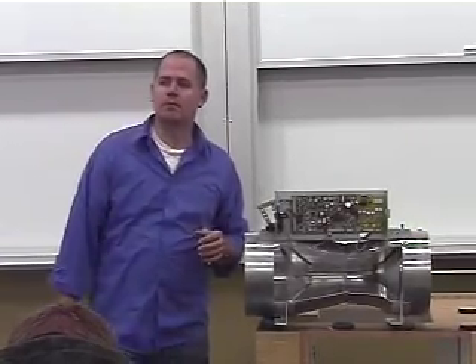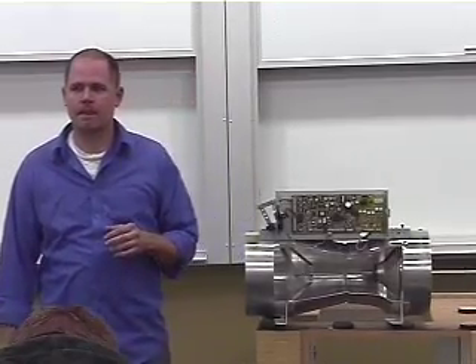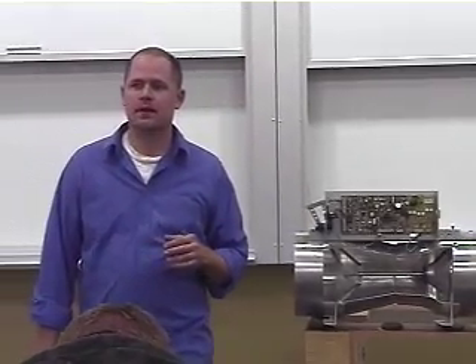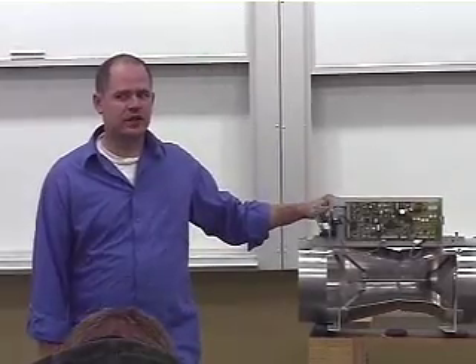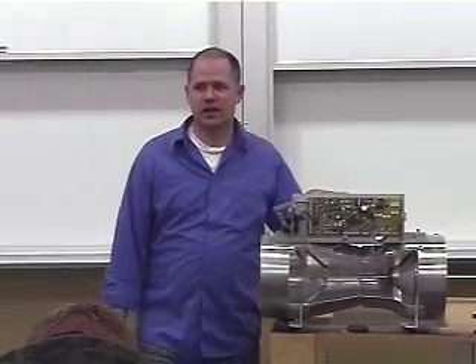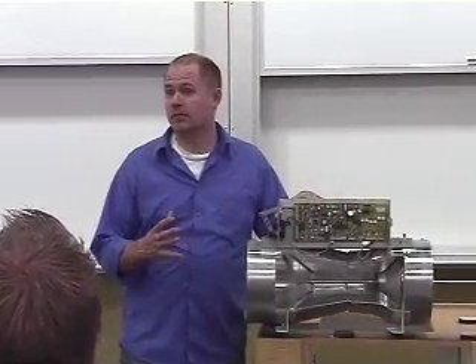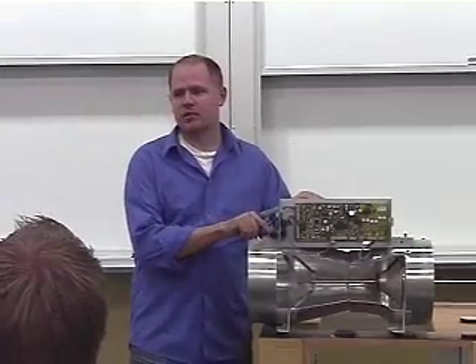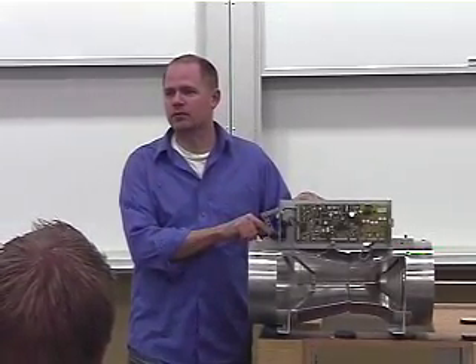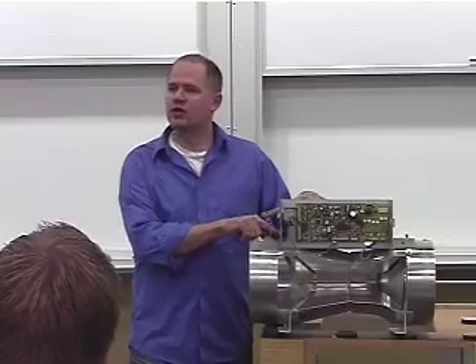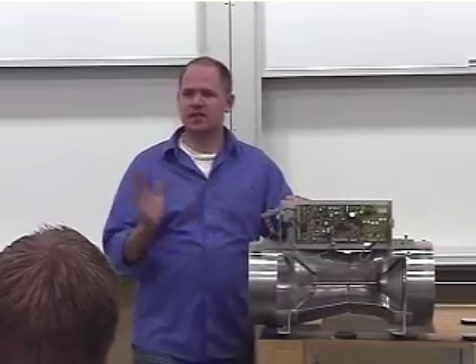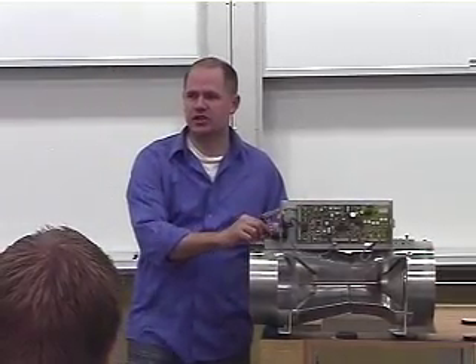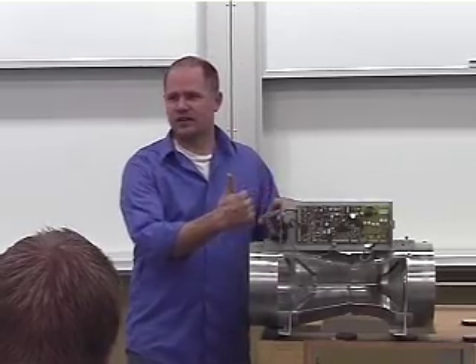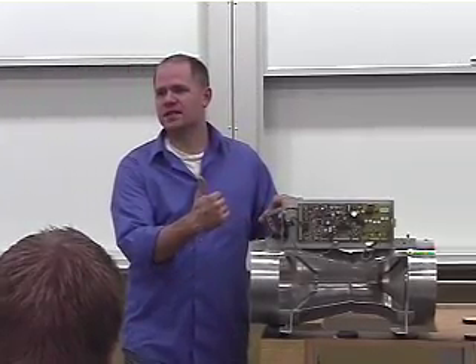Do they operate on a 0 to 10 volt? The actuator does not. The actuator is a modulating or a 3-point floating, but it gets feedback from the potentiometer to know right where it is. So that's how it knows where it is and gets to the right position, is it sees the voltage of this potentiometer change. So it knows, okay, I've got this in this position, and it drives it until it gets there.